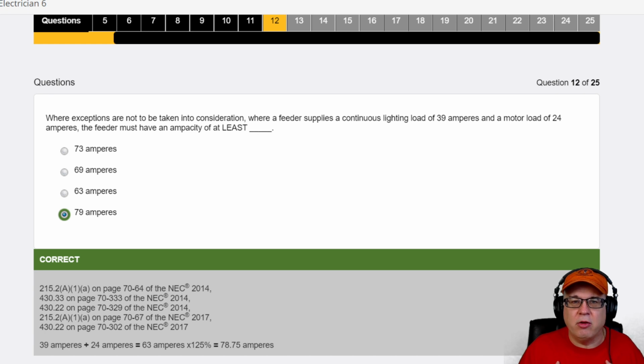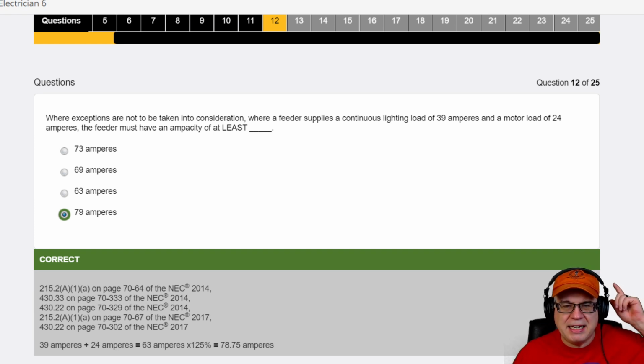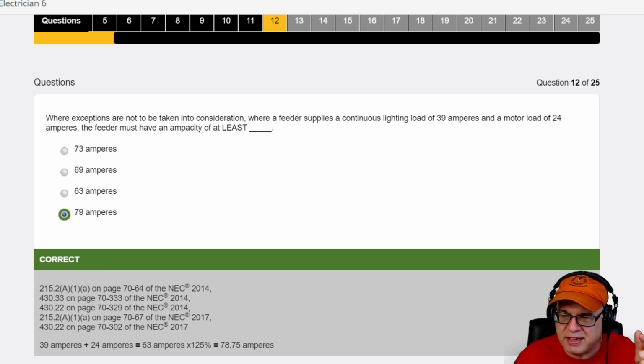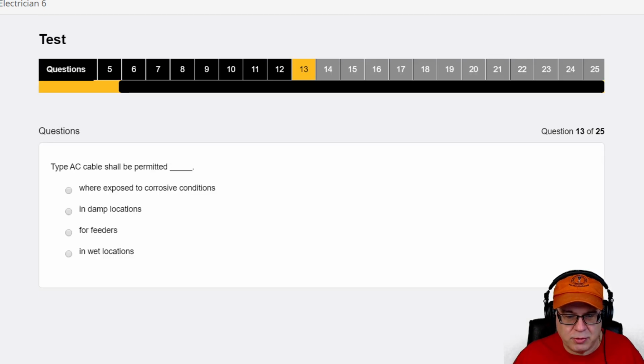And since I know motors get sized at 125%, and I know I'm going to size my load, basically I take each value and do it at 125%, or I can take them, add them together, and do it at 125%. Both of them, incidentally, were being treated as continuous loads, so either way you work it, it comes out the same. That's the beautiful thing - there's multiple ways to always skin a cat. Don't skin cats, I'm a cat lover. So there we go, all right, let's do another one.